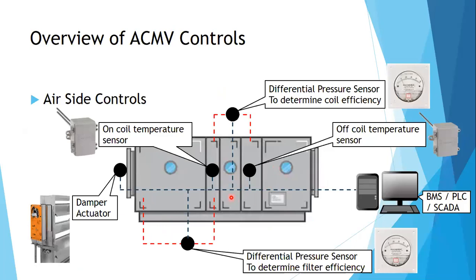Another one, differential pressure sensors. Your air handling unit has differential pressure sensors. There's one here monitoring before the coil, or what we call on coil, and after the coil, or off coil. So on-coil and off-coil pressure difference. We're also monitoring the pressure difference between the coil and the mixing box, before and after the filters. And we're also monitoring the damper actuators.